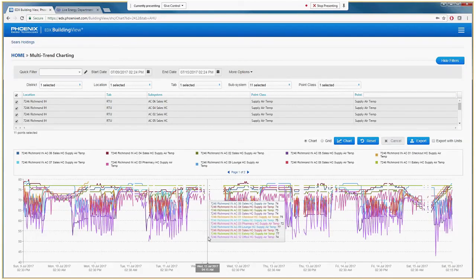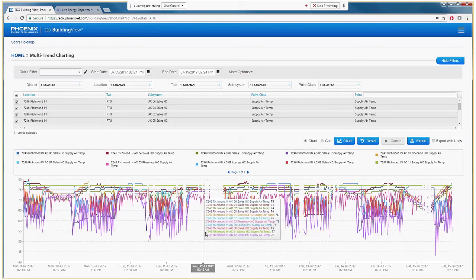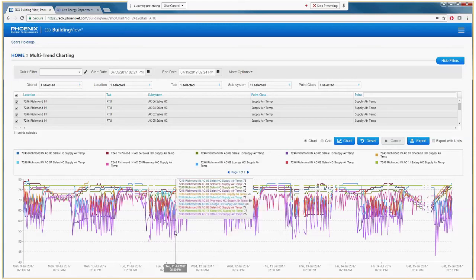Now this data, while there's a lot here, it's more useful than the compressor 1 data, being that I can see that we only have really one unit that's giving a supply air temperature below 60 degrees for this week. And it's really difficult to cool a store, and certainly very difficult or near impossible to remove humidity from a store when our supply temperatures are above 60 degrees. So we'll see a little bit in the next helpful hint of how that impacts this facility.